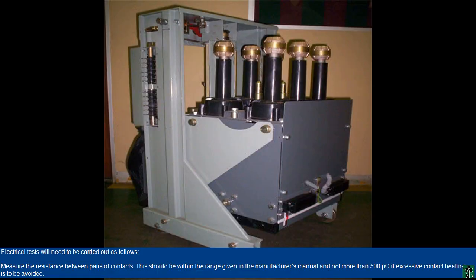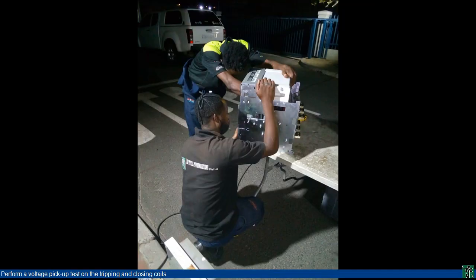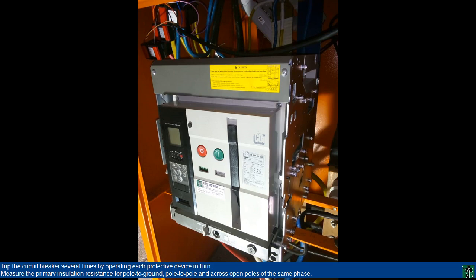Electrical tests will need to be carried out as follows. Measure the resistance between pairs of contacts. This should be within the range given in the manufacturer's manual and not more than 500 microohms if excessive contact heating is to be avoided. Perform a voltage pickup test on the tripping and closing coils. Trip the circuit breaker several times by operating each protective device in turn.